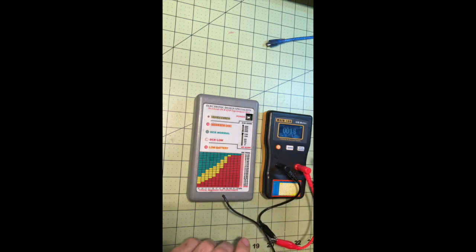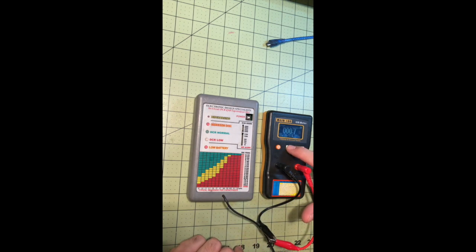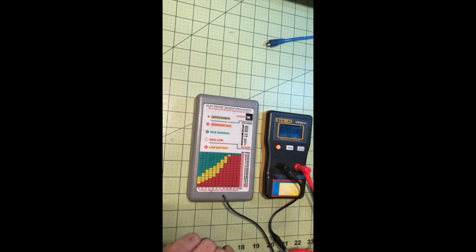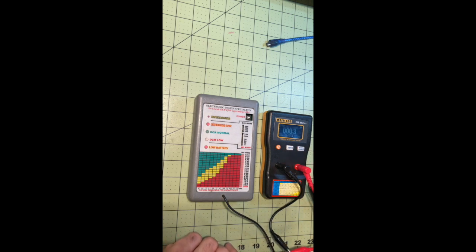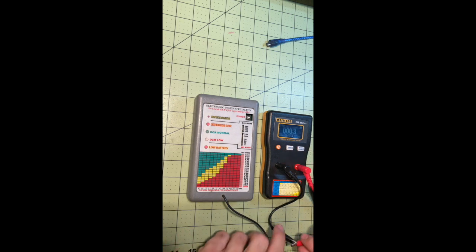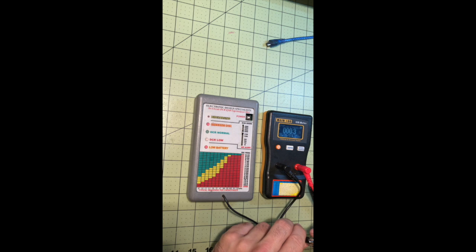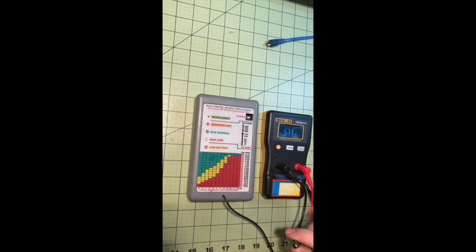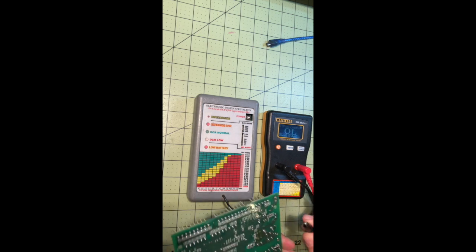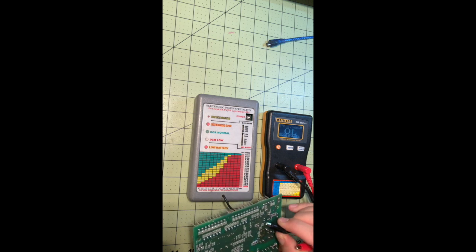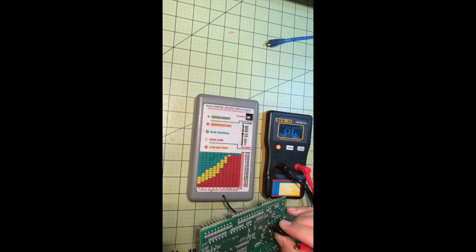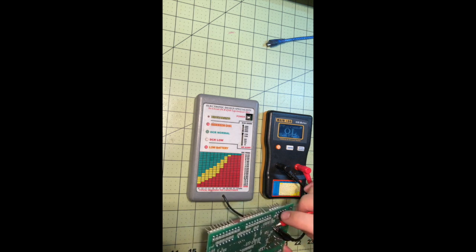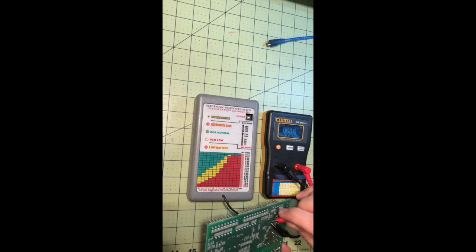All right, to zero this one out you want to press and you want to short the leads together. It says zeroing please wait and then it shows you about zero. So we're good now. Just calibrates it and black or red doesn't matter what goes to where.